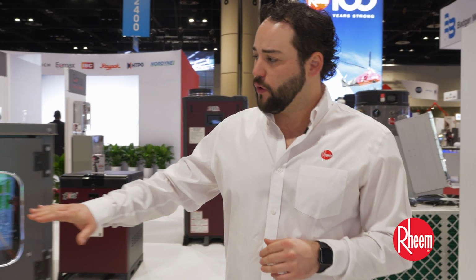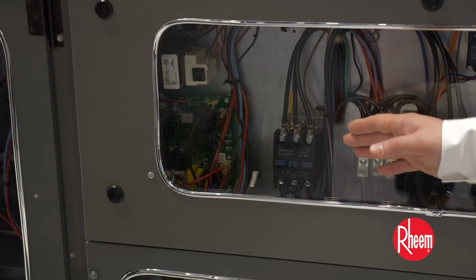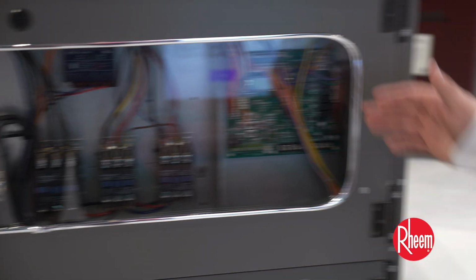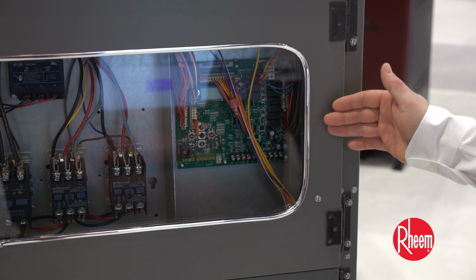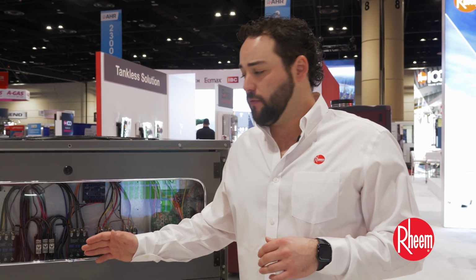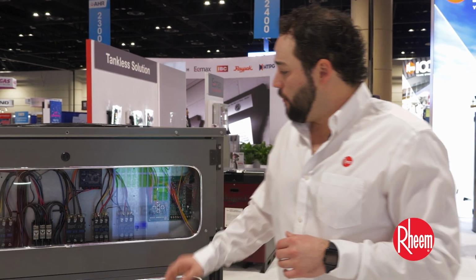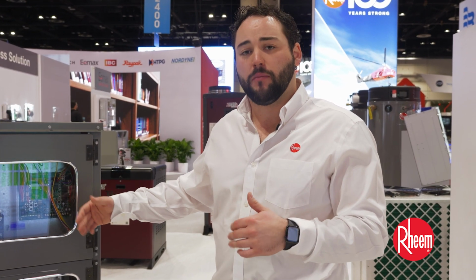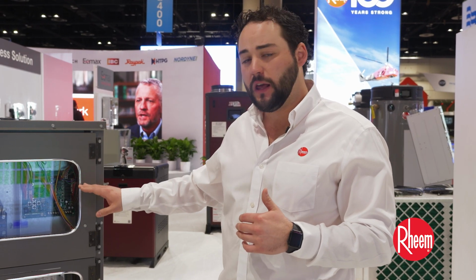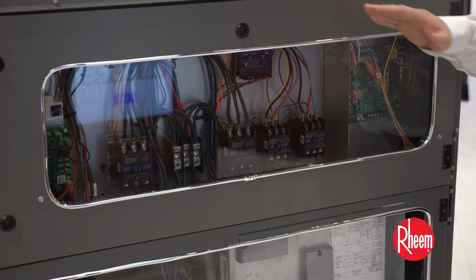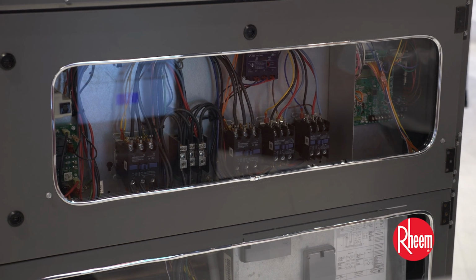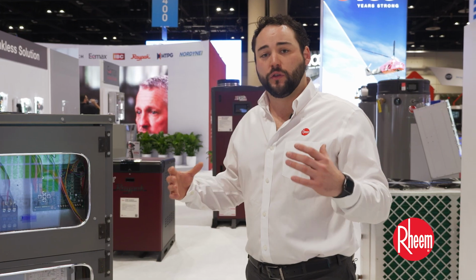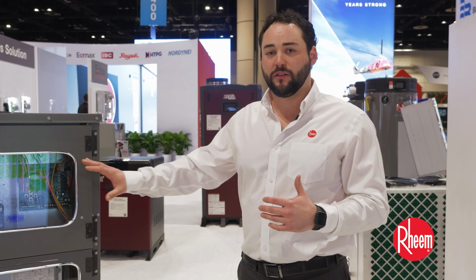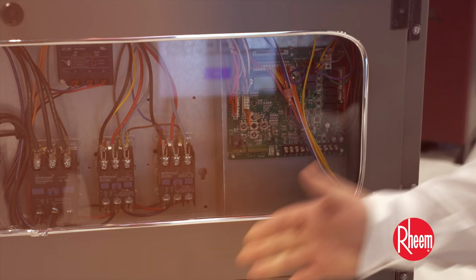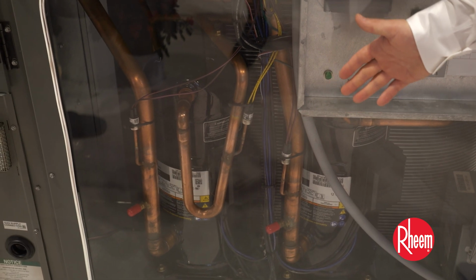What you'll notice here, starting with the control section, is we have two different control boards. We have our Core Command 24-volt non-DDC board, and then our Clear Control DDC microprocessing unit. What this allows the contractor to do in the field is actually see the fault codes at the unit, not have to go searching. But if they do buy or install the microprocessing unit, they're able to actually set up the unit and go into deep parameters right there in the field. And on the back side of this panel with easy access, they would be able to see the entire electrical schematic right there in the field, not have to go searching for it, and easily service and set up this unit on a rooftop.